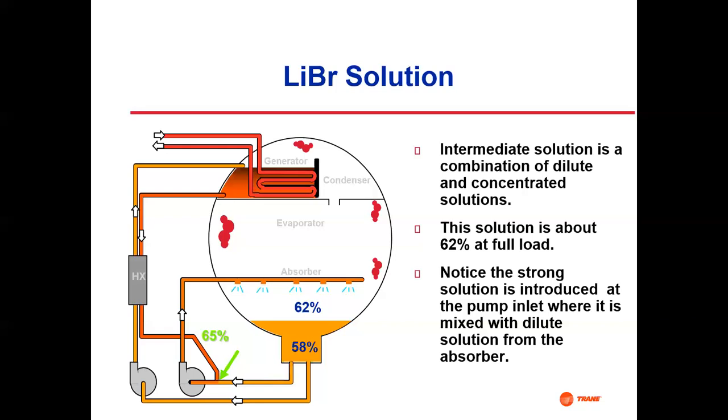When you go through a pump impeller, you don't have to worry about getting it mixed over here. That's a good place to put it in. So we're at 62% here, so it still has the ability to absorb some water vapor, which is generated up here, and it keeps sucking up that water vapor, which keeps the pressure low down here. And then when this stuff is saturated, it just lays down here. There's a sump that collects it at the bottom.